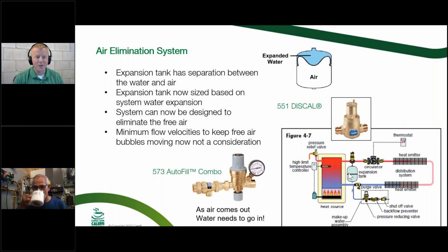Yeah, with the air separators, they all have a 1/2 inch, especially on the smaller residential size ones, they have a 1/2 inch tapping on the bottom of them. That's perfect for adding an expansion tank. And ideally you always want to be pumping away from that expansion tank. You always want to be pumping away from your air separator in order to get the lower pressures at those points. And that's a great place for your point of no pressure change, which we'll talk about in a second.